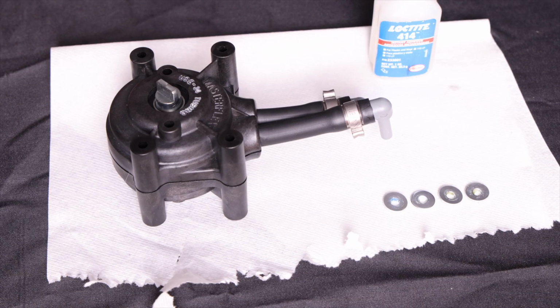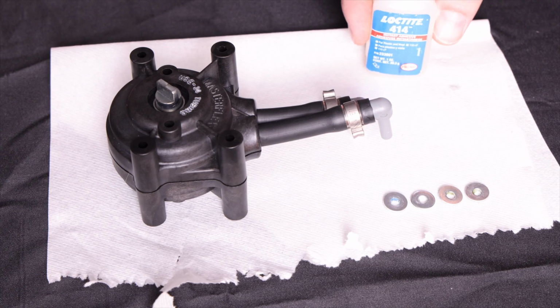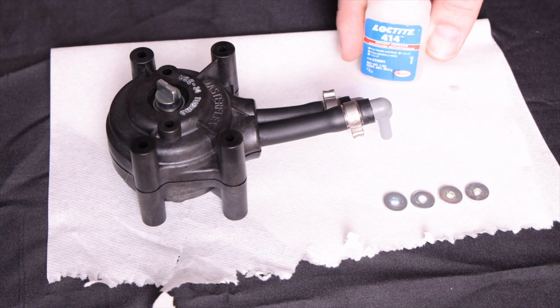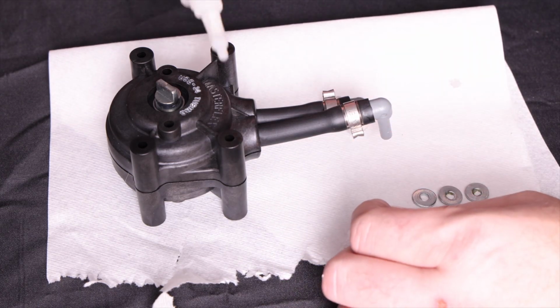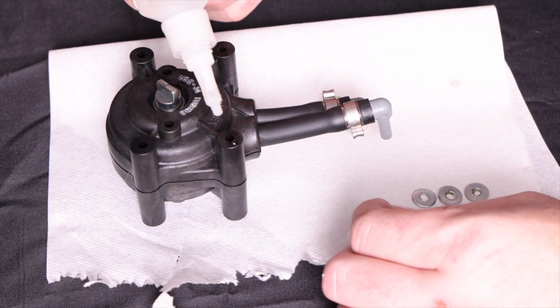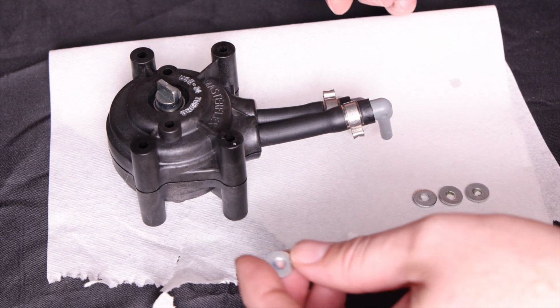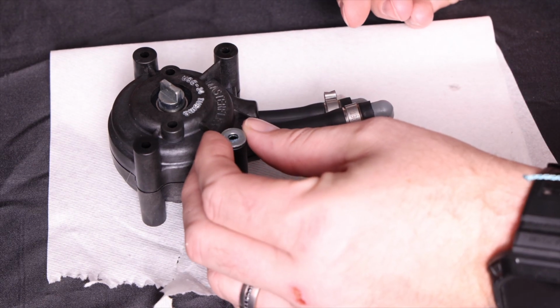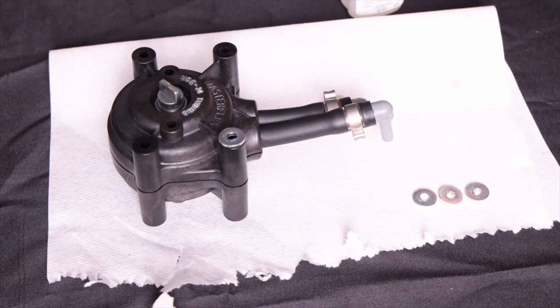With our tubing now replaced, before we reinstall the pump assembly, a helpful tip: use a small dab of super glue on the washer. Do a dab on the pump, and place the washer center. Do this for the remaining washers. After applied, let sit for about a minute before applying the pump back to the machine.